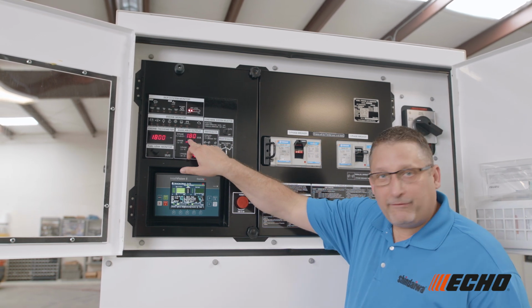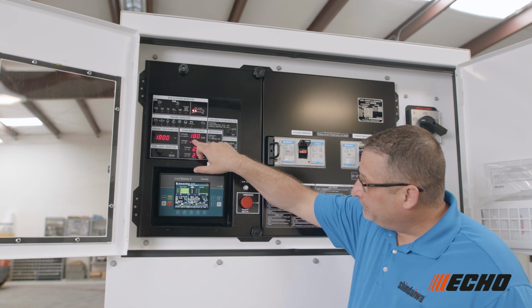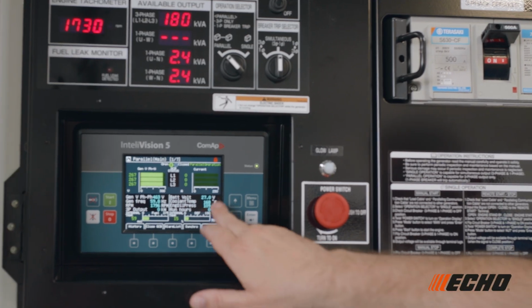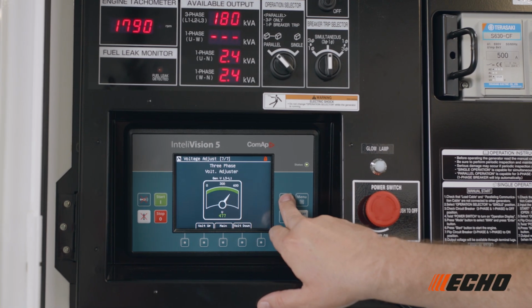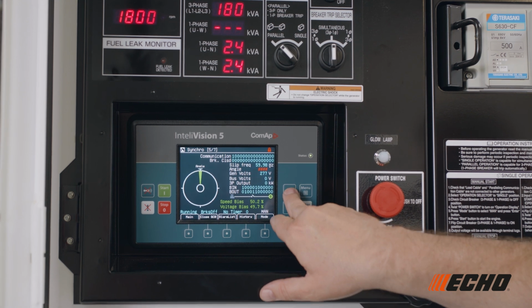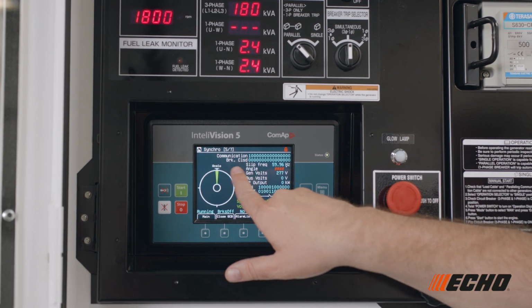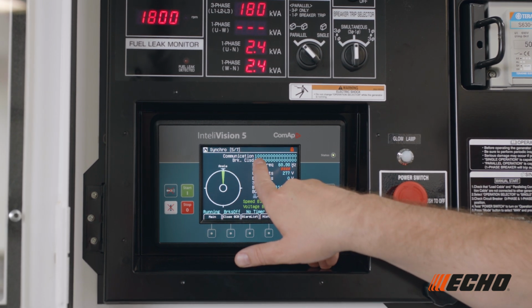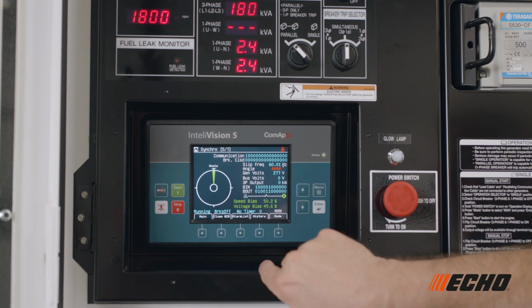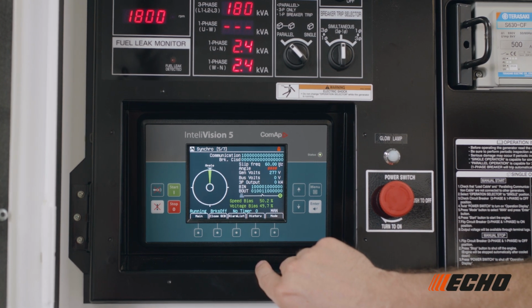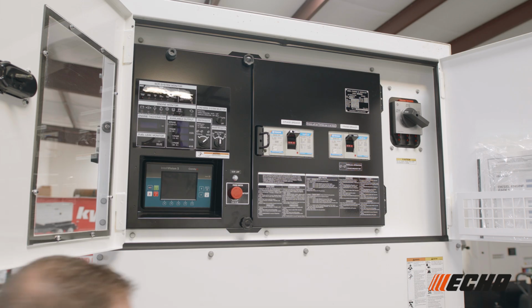We have 180 kVA of 3-phase load that's available. As I rotate through the screens, this is your sync screen. You'll notice that we have this set as gen priority number 1. That's located here in the first digit. Let's go ahead and start the other machine.